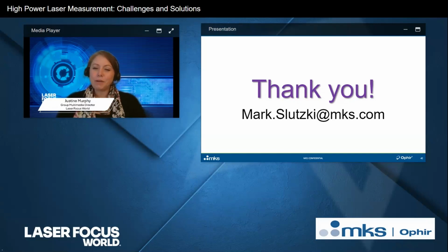How do you compare the thermopile to the integrating sphere, and what are the pros and cons? An integrating sphere, for those of you who aren't familiar with it, is basically a hollow sphere, the inside of which is white, diffuse, and highly reflective, either a coating or an insert. When a beam of light comes in through an open part of the sphere, it bounces around in all directions an infinite number of times, quote unquote, so that it gets uniformly distributed throughout the inside of the sphere. And then we've got a sensor, like a detector, built in. The detector obviously sees only a small bit of the total power that came in.